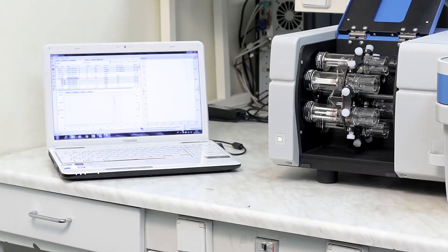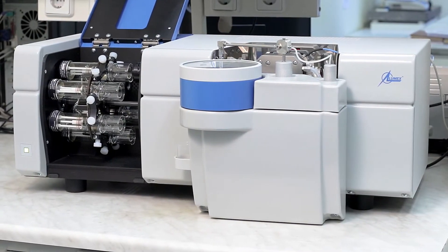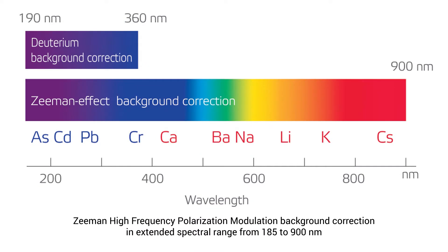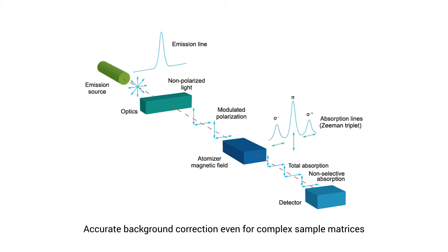Next, we will show you some of the main features of MGA-1000. The Zeeman High Frequency Polarization Modulation enables background correction in whole spectral range from 185 to 900 nanometers. This technology is responsible for simultaneous measurement of total and background absorptions.